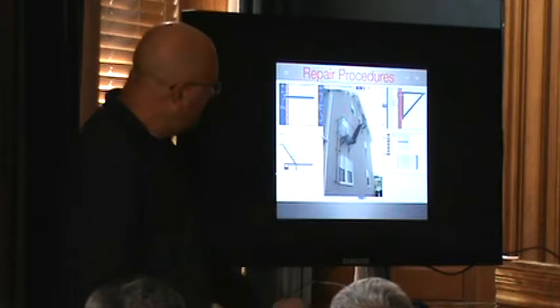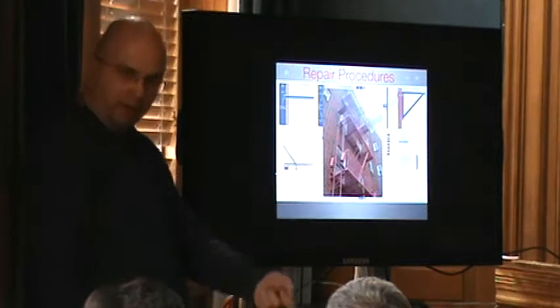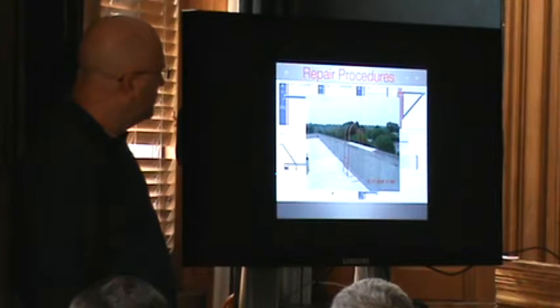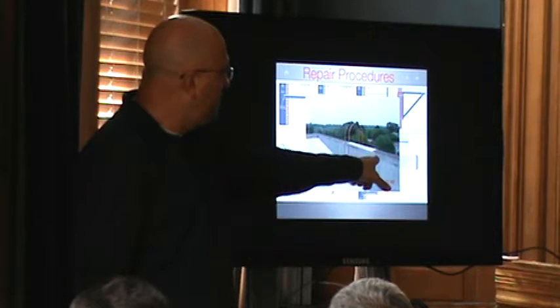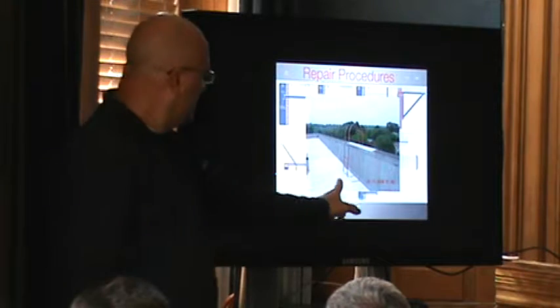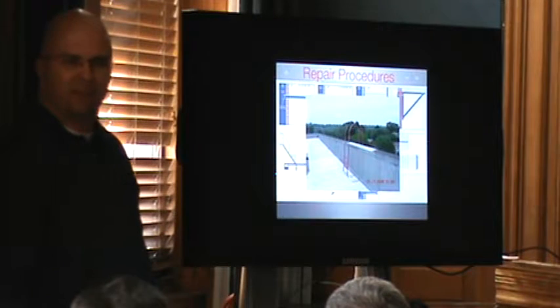Ladders on the side, fixed ladders. Ladders with weight systems, so they have to drop 2 to 3 feet per second to hit the ground and stay down. Roof ladders, a lot of times they rot out here. Firemen are the only ones testing this, but under that rule where you inspect it every year, management has to climb up and over these things to basically assure the firemen that the fire escape is in good order.